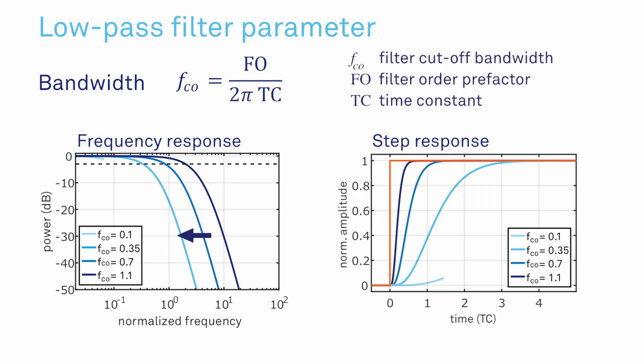The low-pass filter is defined by two parameters: bandwidth and order. The bandwidth indicates the cutoff frequency and is inversely related to the time constant. Lower bandwidths give more signal-to-noise ratio but increase the acquisition time.